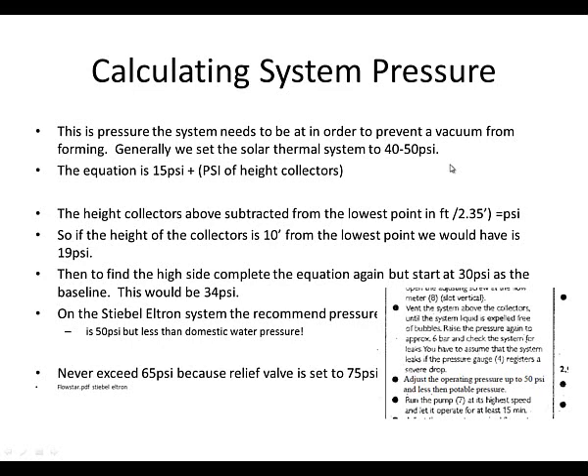This portion is going to be calculating system pressure. This is to calculate what to pressurize the closed loop to, to give us the most ideal heat exchange and to prohibit a vacuum from forming. A few critical ideas to remember: if we do not set the pressure correctly, what will happen is at the top of the collectors we will actually produce a vacuum. That vacuum will then induce bubbles — oxygen or air bubbles sucked into the system — or we'll get a vacuum lock at the top. We do not want that.